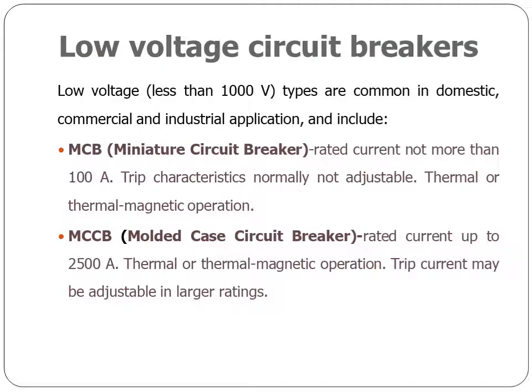There are three types of circuit breakers: low voltage circuit breaker, medium voltage circuit breaker and high voltage circuit breaker. Now we will discuss low voltage circuit breakers first. Low voltage, that is less than 1000 volts, types are common in domestic, commercial and industrial applications and include the MCB. MCB means miniature circuit breaker. Rated current not more than 100 amps. Trip characteristics normally not adjustable. Thermal magnetic operation.